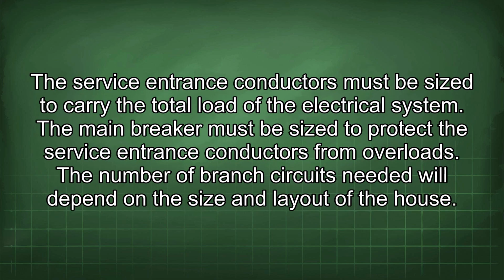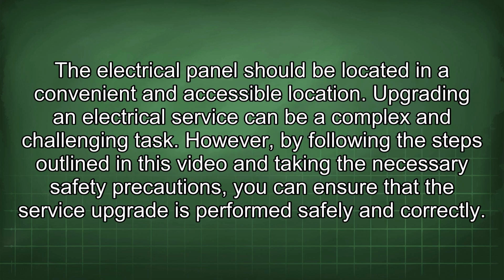The service entrance conductors must be sized to carry the total load of the electrical system. The main breaker must be sized to protect the service entrance conductors from overloads. The number of branch circuits needed will depend on the size and layout of the house. The electrical panel should be located in a convenient and accessible location. Upgrading an electrical service can be a complex and challenging task. However, by following the steps outlined in this video and taking the necessary safety precautions, you can ensure that the service upgrade is performed safely and correctly.